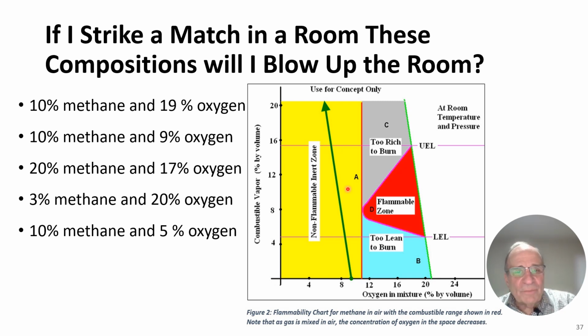Let's say I had 20% methane, so I'm up here, and 19% oxygen. That puts me out to here. Will I have an explosion? No, I'm too rich. Let's say I had 3% methane, so I'm down here. And I could tell without even looking at whatever the oxygen content is. 20% oxygen, too lean to burn. How about 10% methane and 5% oxygen? 10% methane, 5% oxygen. I will not burn. I'm in the non-flammable range.